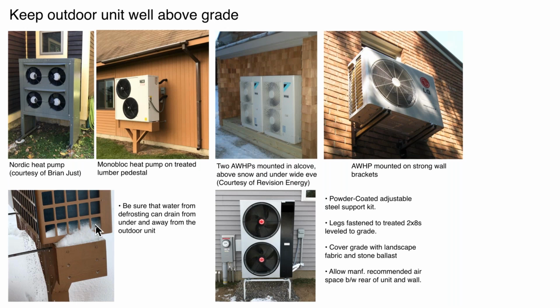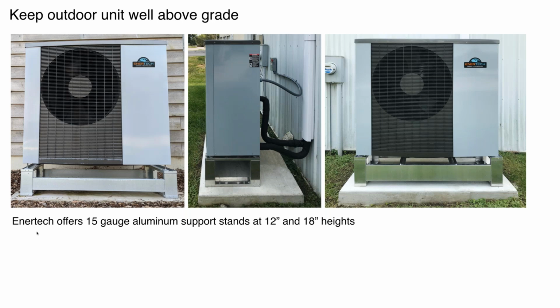Again, the Enertech unit does have a tube, and it does have a heater in it so that it doesn't form ice within the unit, but make sure that you provide a provision for that condensate to go away. And you can see when this unit, this is a nominal 4-ton unit, goes through a defrost, it probably drops, I'm going to say 2 pints at least of water. Okay, so keep it up off the ground, make sure that condensate can drain away from the unit. This is the stand that Enertech has available for the heat pump. It's a heavier gauge aluminum stand. You can see it's on a concrete base there. You know, for an area with moderate snowfall, that would be adequate. If you live in the Tug Hill area of upstate New York, they get snow measured by the foot up there. So it's not uncommon to see 3 or 4 feet of snow on the ground. And in places like that, you want to get that unit up even higher.